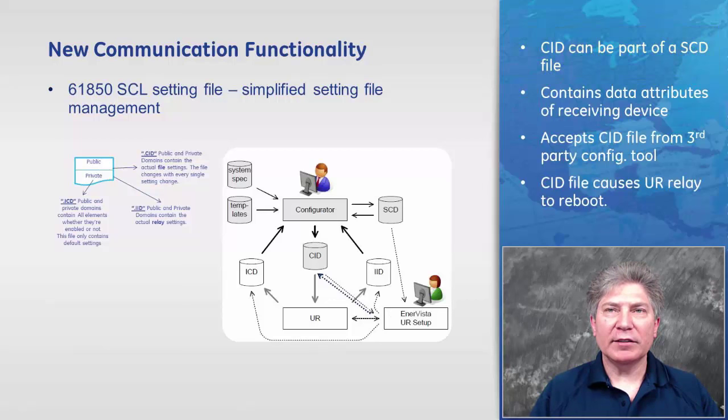When importing an SCD file, the EnerVista UR Setup strips out the UR relay portion and creates and sends a CID file to the UR device when IEC 61850 settings are involved. The CID file includes all data attributes of the target IED, the control block information and settings, and completely reprograms the receiving device.